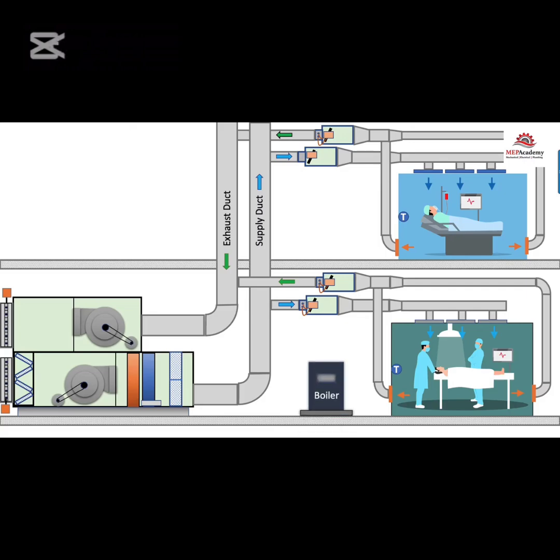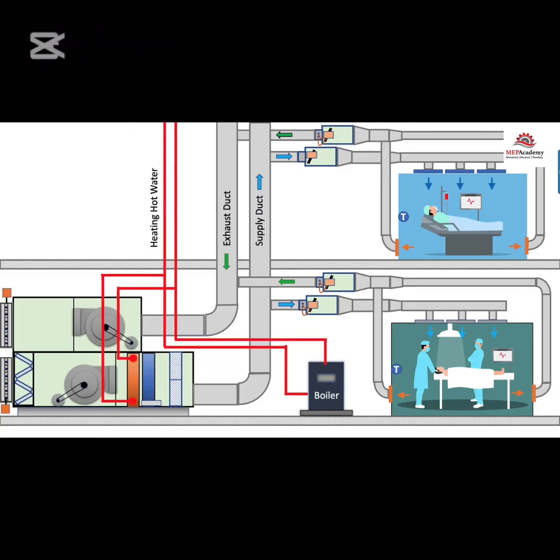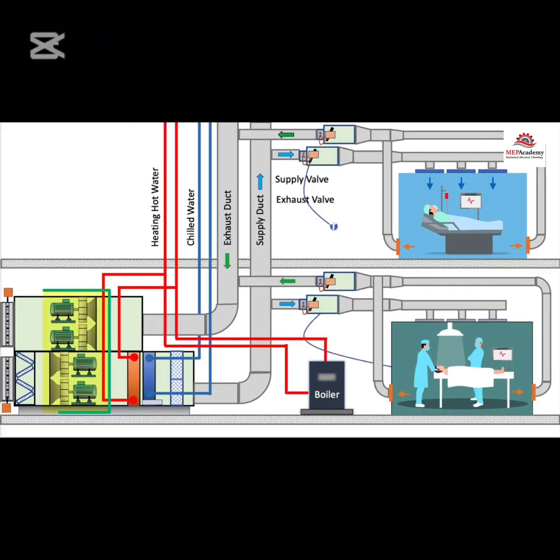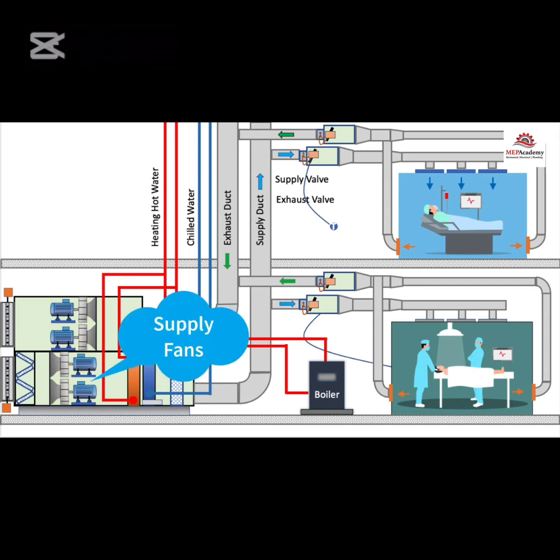And then the contractor will drop in a boiler, hook up all the hot water piping to our hot water coil, and then connect from the chiller to the chilled water coil. Or if you're using a compressor, you can run your DX lines. And on the heating hot water, if you're using steam, you can run the steam lines. Now we'll upgrade the fans. We'll put in plenum fans because they provide better acoustics and allow for some redundancy in case a fan burns out. As you can see, we added them on the supply inlet and on the exhaust.